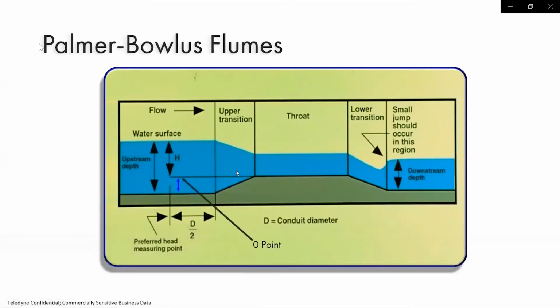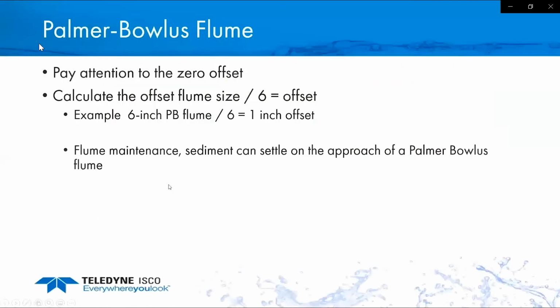And so if you could stop the flow of water, you'd see that you'd have water pooling up right here, and this would be your 0 level. You set your level to 0, be perfect. But usually you can't do that. So what you'll do is you measure the overall water height, subtract this offset, and then that will be your corrected level. And one of the calls I'd get a lot of times is that somebody says their flow rates are all of a sudden higher after somebody went out and calibrated. Well, the problem is that they did not account for that offset.